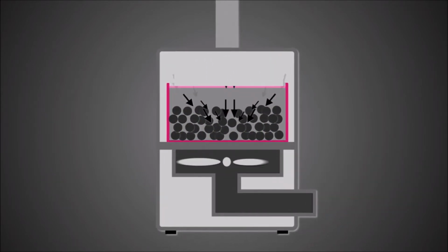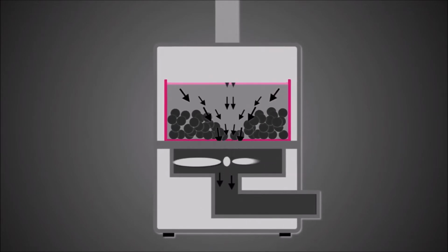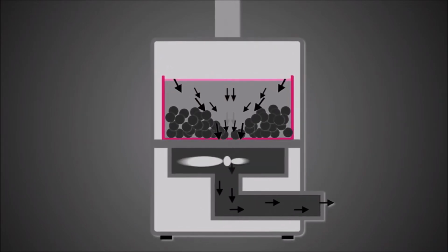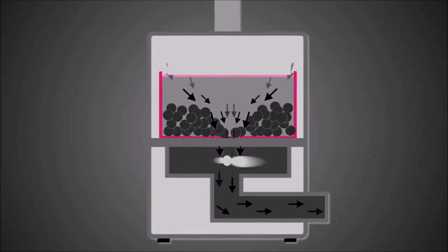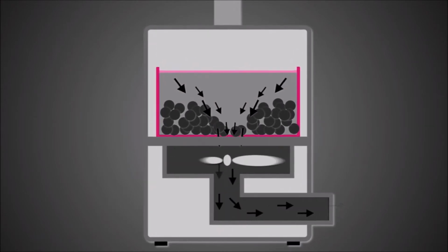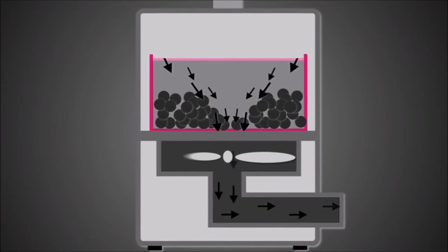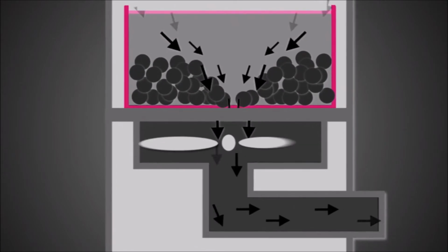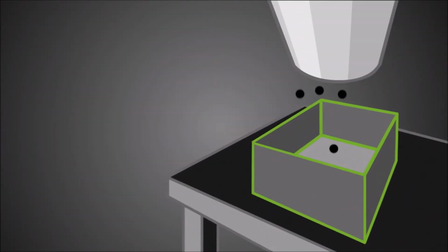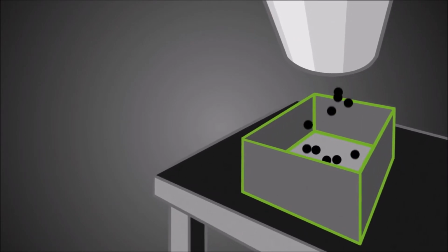Further compacting occurs when the filter is fitted and put into use. The air that passes through the media creates a thinning of the bed, causing tunneling and subsequent bypass. The problem is often attributed to premature carbon saturation, where in fact it is a construction fault in the filter manufacturing process. BOFA use a vibrating table to guarantee all settlement takes place on assembly.